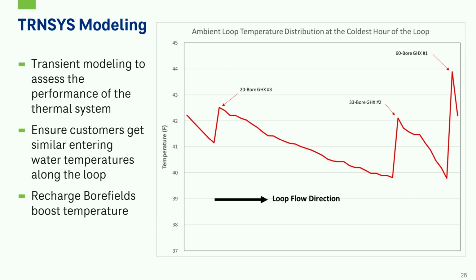And so this graph on the right is showing the temperature distribution at the coldest hour within the loop. If we start at the 20 borehole ground heat exchanger number 3, we can see it decreases along the line, and that's when each customer that's taking water or the fluid with propylene glycol from the ambient loop, running it through their heat exchanger, which will then go to their heat pump and then come back into the loop, returning with slightly lower temperature.